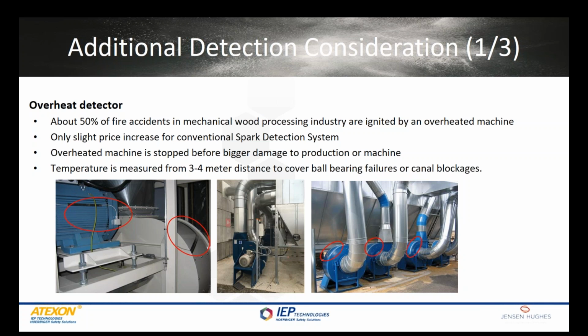that we use. The first one is the overheat detector, which is used for detecting, for example, ball bearing failure of a dust extraction fan. It is known that about 50% of fire accidents in the woodworking industry are ignited by an overheated machine. It is important to measure temperature from a long distance. For example, dust pipe blockage can be measured from the perimeter of the fan, and ball bearing failure on the sidewall of the fan.